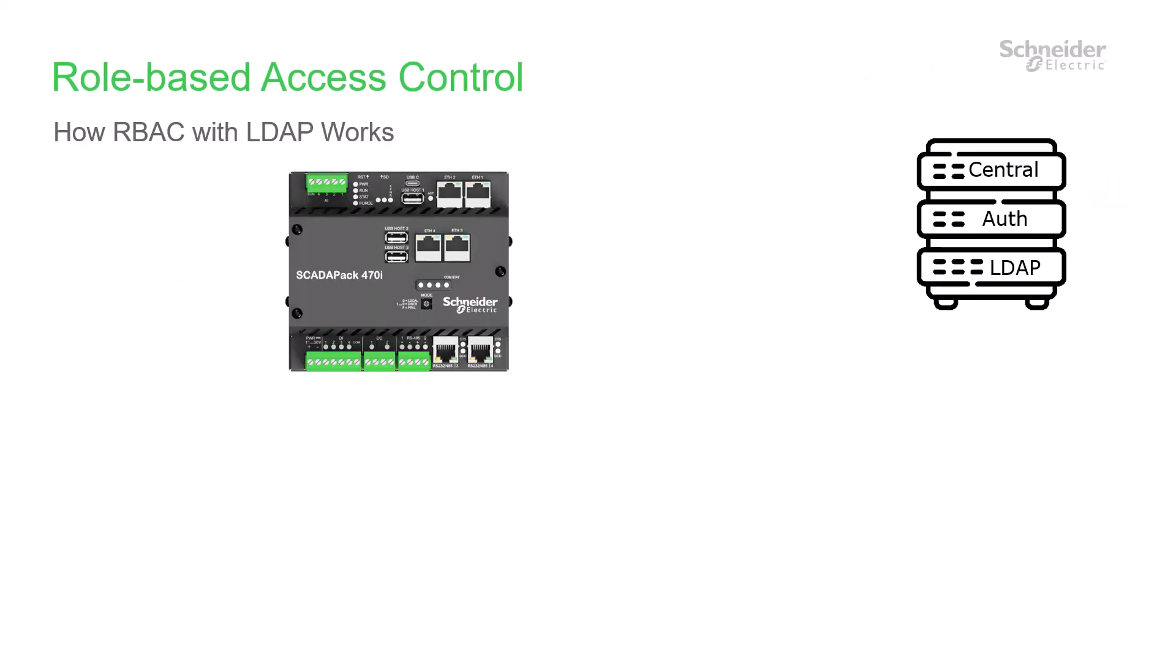You can configure each SCADAPack 470i or 474i to communicate with the AD server using LDAP, the Lightweight Directory Access Protocol, or LDAP Secure, over an IP connection. When you attempt to log into an RBAC-enabled SCADAPack, the RTU transmits your credentials to the Active Directory server via LDAP or LDAP-S.